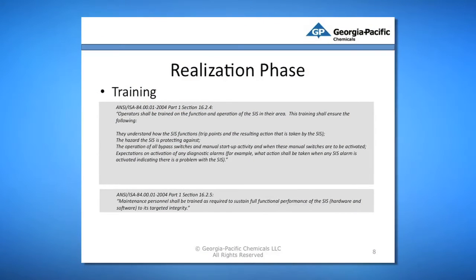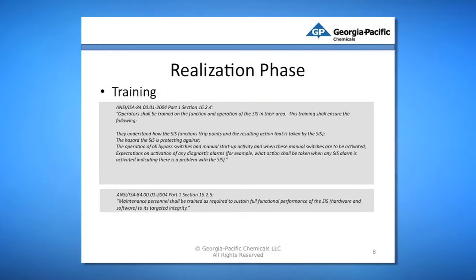A training plan needs to be developed for operating personnel interfacing with the safety instrument system. A combination of training methods can be utilized. We developed computer-based training modules, had hands-on training with the simulator before the system was installed in the field, and then developed all the standard operating procedures for the system.